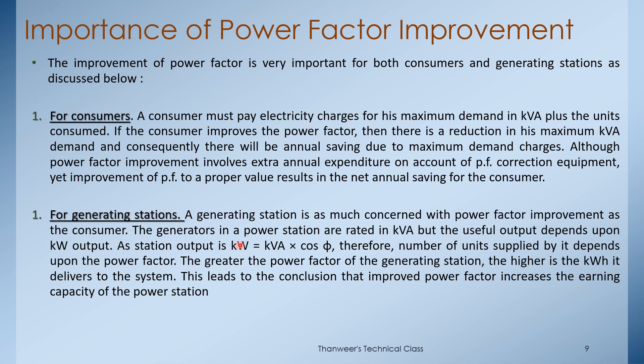For a generating station, generators are rated in kVA, but the useful output depends on kW output. kW = kVA × cos(phi). Therefore, the higher the power factor of the generating station, the higher the kWh it can deliver to the system. This leads to the conclusion that improved power factor increases the earning capacity of the power station.